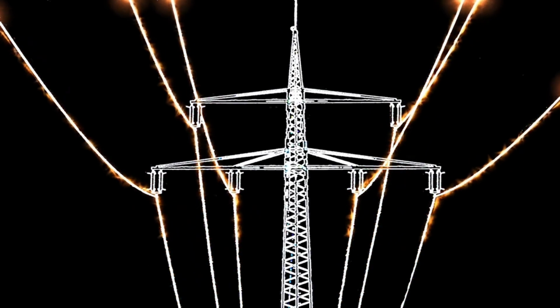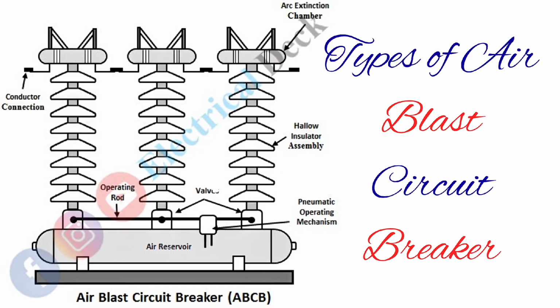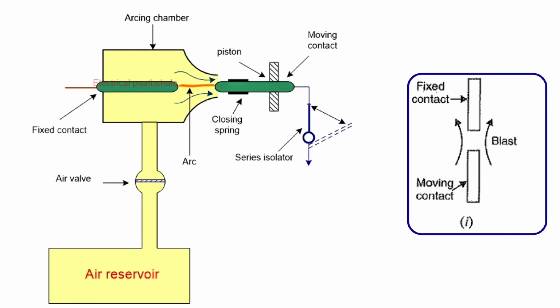As we have covered the working principle of ABCBs, now we will analyze the types of air blast circuit breakers. Air blast circuit breakers, ABCBs, are classified into several types based on the direction of the air pressure that is used to extinguish the electrical arc. The type of ABCB used depends on the specific application and the requirements of the system. The first type we will analyze is the axial blast type. The axial blast type of air blast circuit breaker is designed where the air pressure is directed along the arc path. This means that the compressed air is blown axially along the arc, which helps to cool and extinguish it quickly. The axial blast is particularly effective in high-voltage transmission systems where fast and reliable arc extinction is needed.